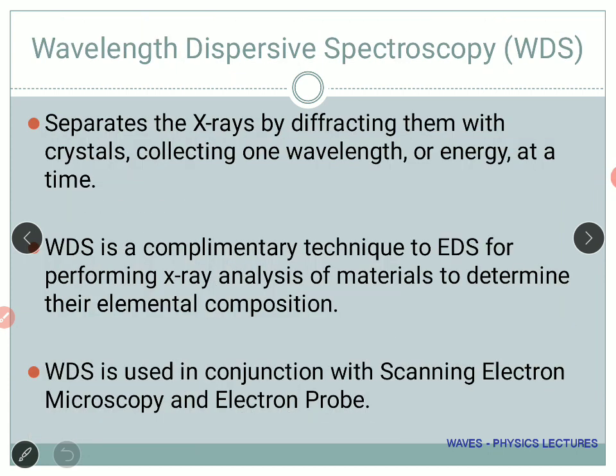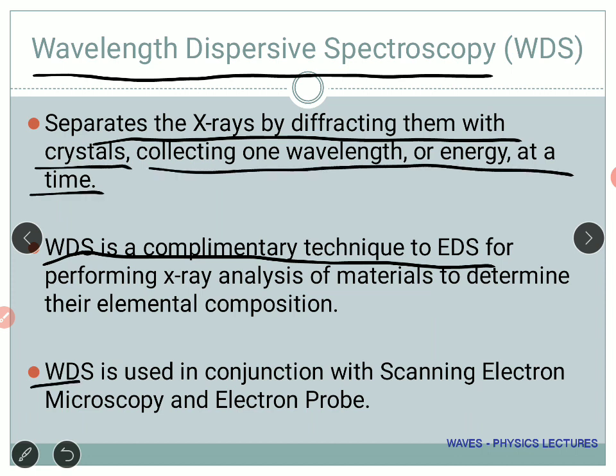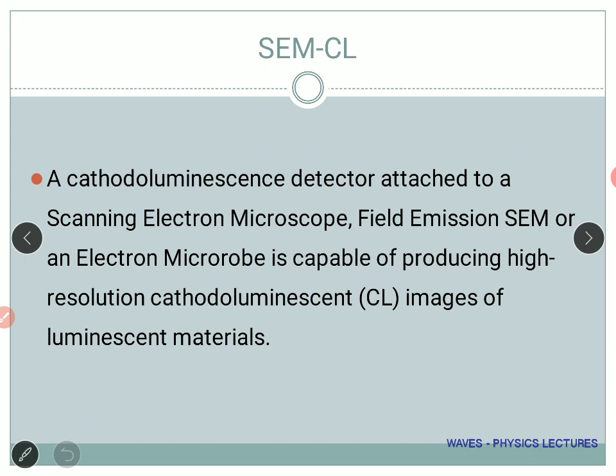Something complementary to EDS is WDS — Wavelength Dispersive Spectroscopy. Energy and wavelength are connected by the relation E = hν or hc/λ, so they are complementary to each other. Only the x-axis of the graph will vary — wavelength instead of energy. WDS basically separates the X-rays by diffracting them with crystals, collecting one wavelength or energy at a time. This WDS is used in conjunction with SEM or an electron probe.